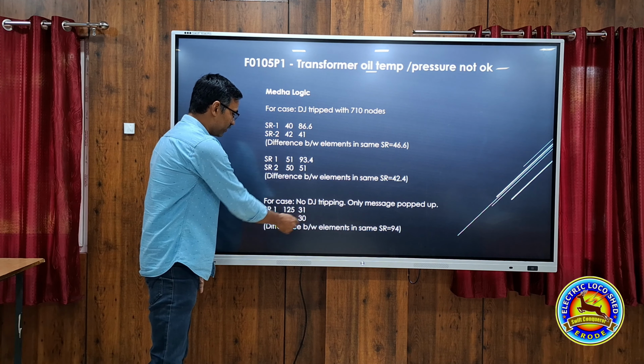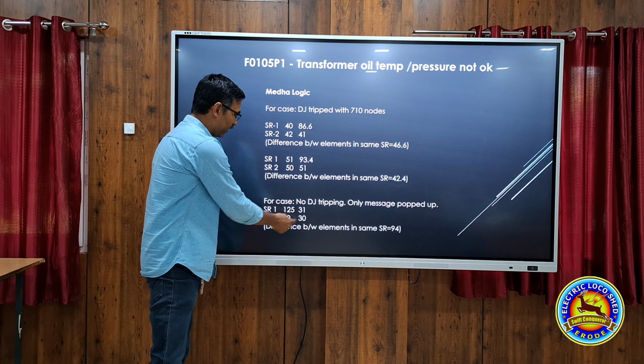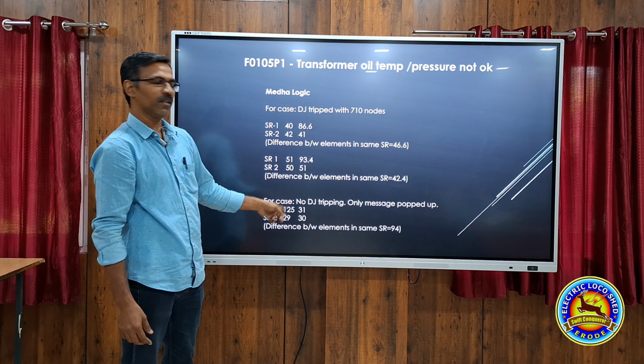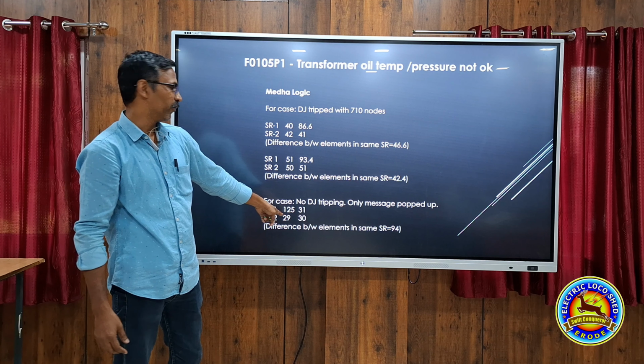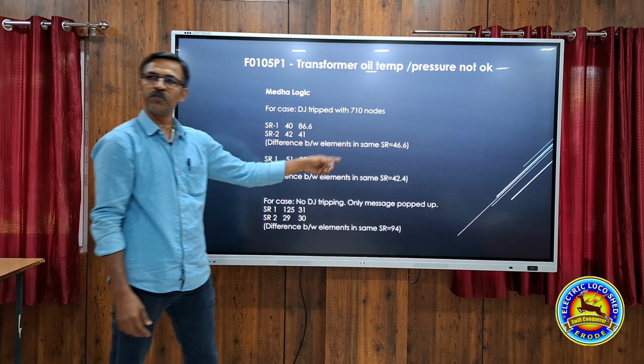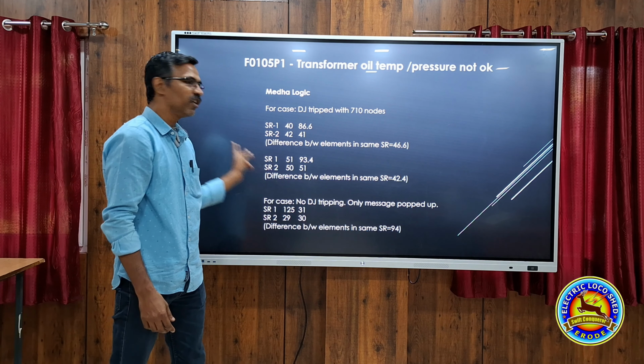The actual temperature value: three sensors are showing values almost correctly, 30, 31, 29. That will be the correct value of the transformer. But one element is malfunctioning. That one is showing 125. So the difference is very huge, more than 50. So that element will be discarded.